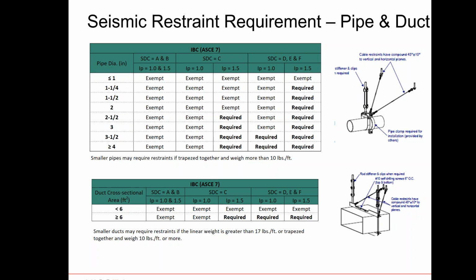And then when you move to seismic design category C, you see that all 1.0 is exempt, and the requirement for 1.5 is anything that is 2.5 inches or larger. Now you can see why the role of the MEP is so important. If you classified everything as 1.5, then anything over 2.5 inches would need to be restrained, and you could have very varying scopes of supply for that building.